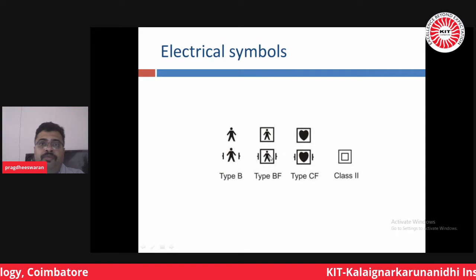If it is within 110 or 120 microampere as per type BF, this is passed. Okay, so that is why I'm saying, before understanding, calibrators are of two types: performance calibrators and safety calibrators. Any equipment you are taking for calibration, you first have to do the performance calibration. Once the performance is ticked, then you have to do the safety calibration. If the safety calibration is also ticked, then you are qualifying the equipment.